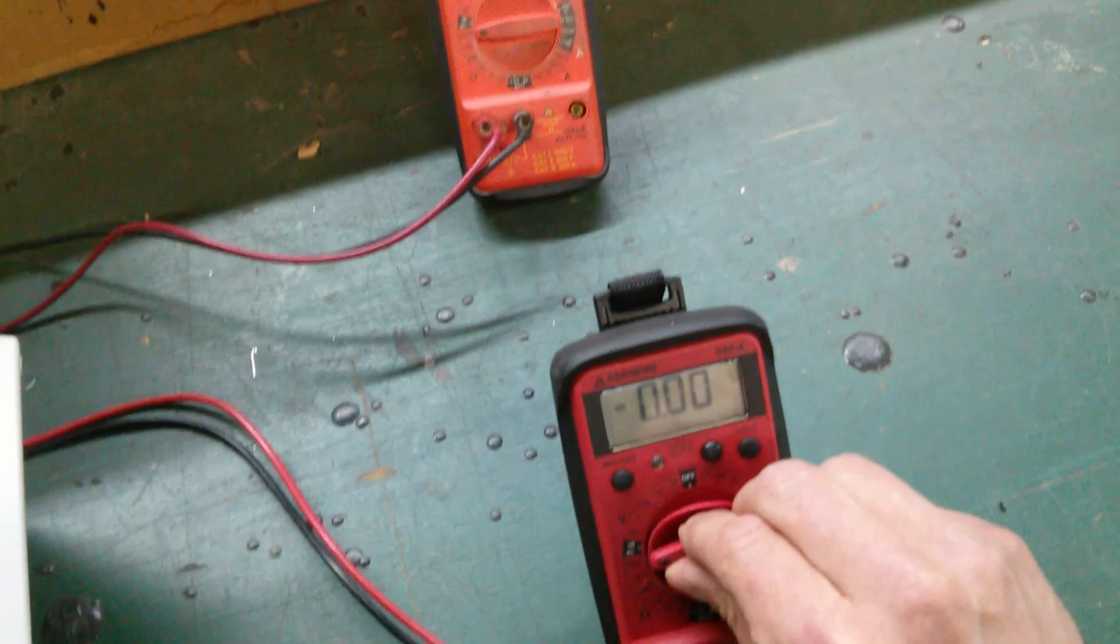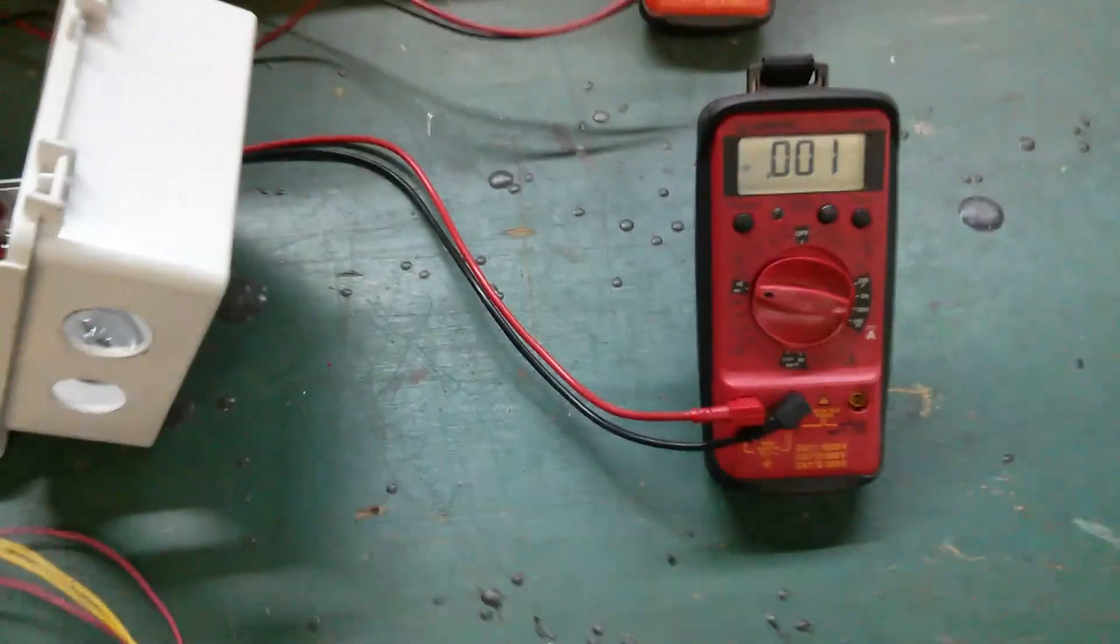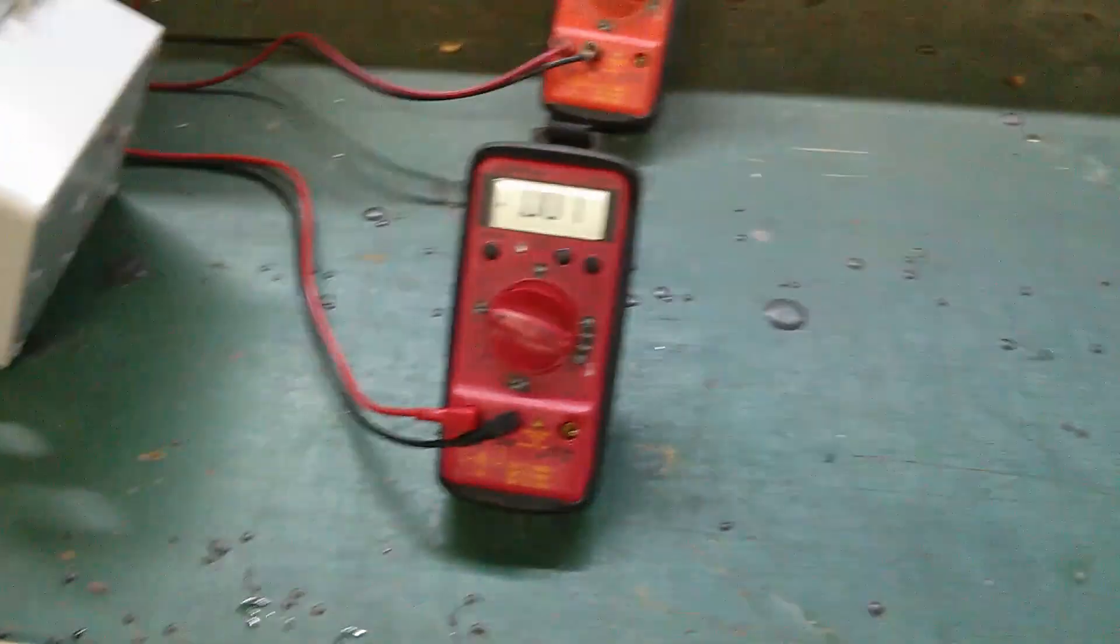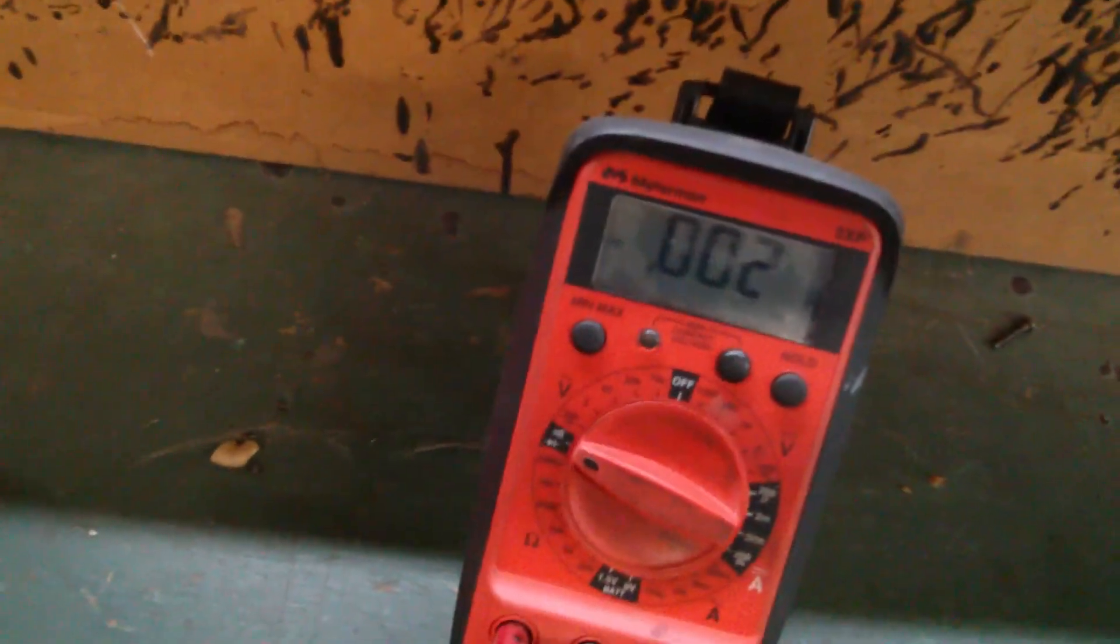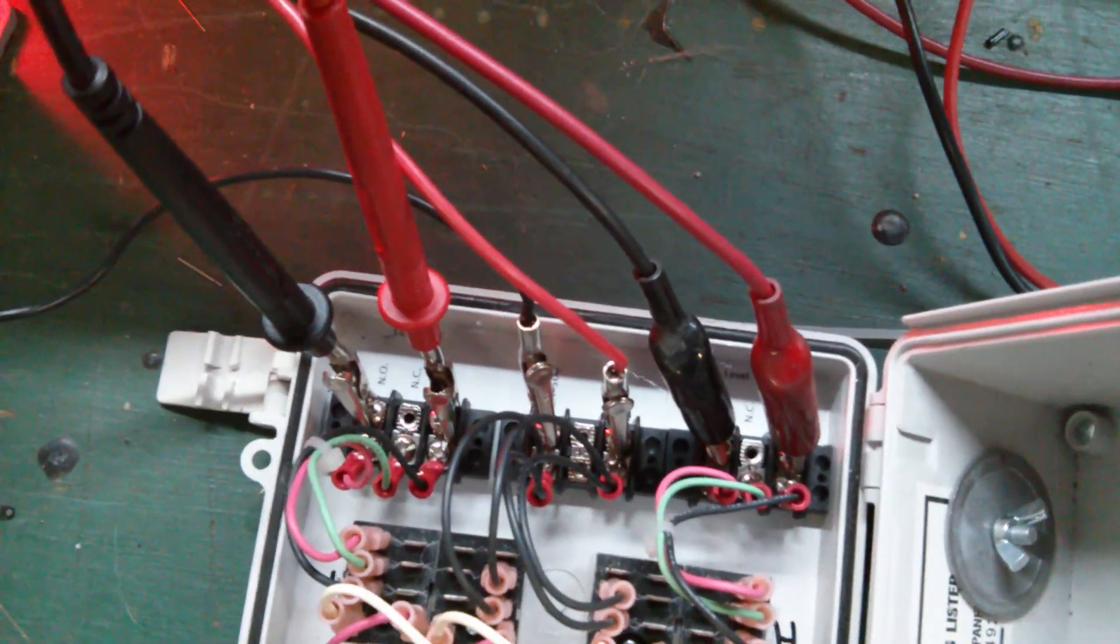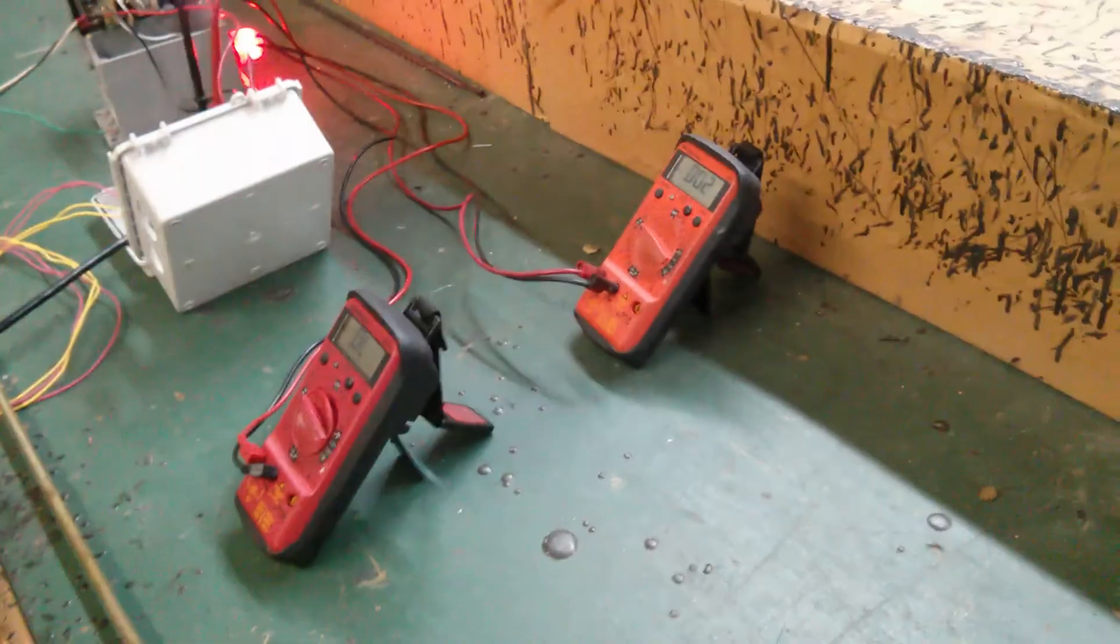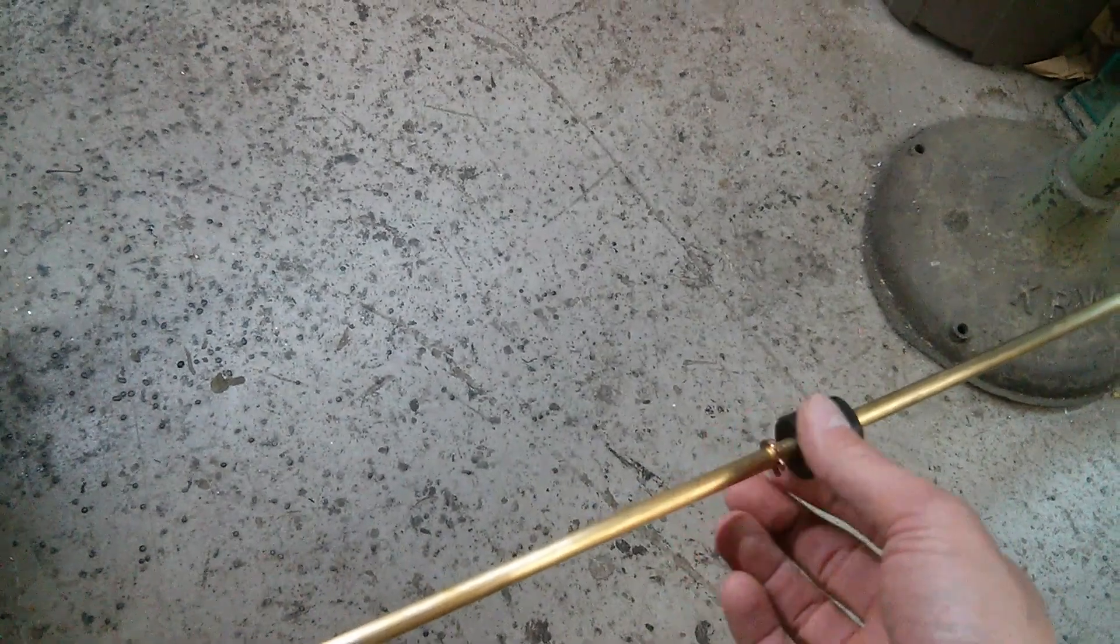For continuity, turn these on. You can see they're both activated right now. Let me put that down, silence the alarm. You can hear the buzzer. It's continuity so that the relay output is activated. As I move the float, you can hear the relay output opening or closing.